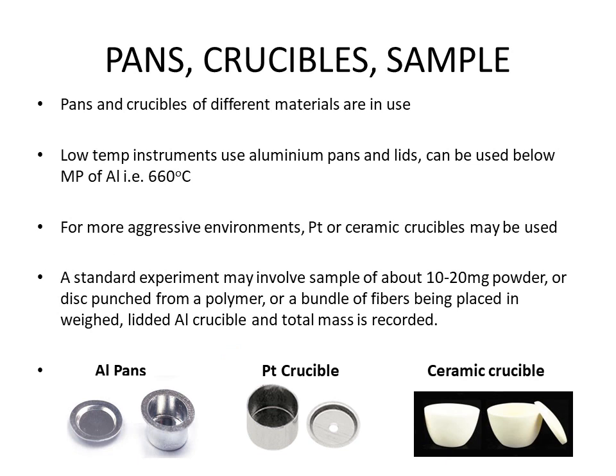Pans and crucibles of different materials are in use. If operating at low temperature, aluminium pans and lids can be used below the melting point of aluminium, which is 660°C. If working at higher temperatures, platinum or ceramic crucibles must be used because their melting points are higher. Here you can see the aluminium pan with lid, the platinum crucible, and the ceramic crucible.